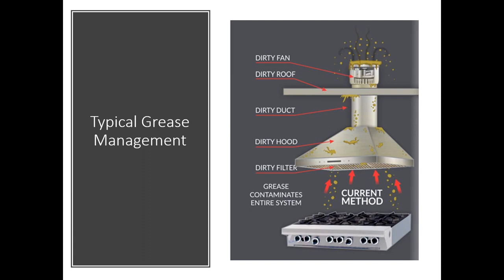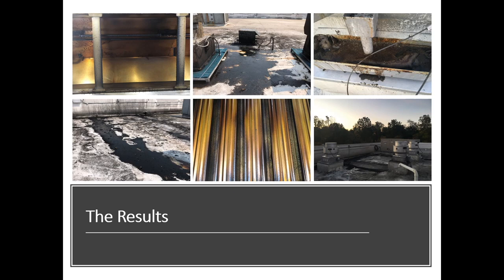So what does all of this look like in real life? Well, the answer is you end up with dirty baffle filters that need cleaned anywhere from daily to a couple times a week by your employees. The hood and ductwork build up and require professional cleaning. Then there is the exhaust fan and the roof that are out of sight, out of mind, that require regular maintenance to be performed as designed, or they break down and require costly repairs.